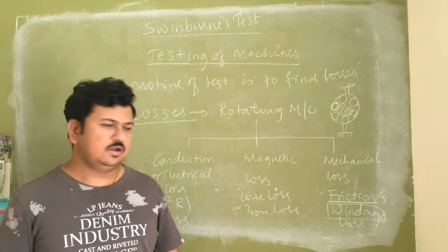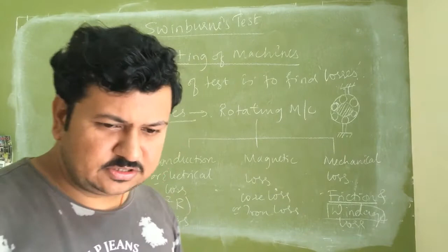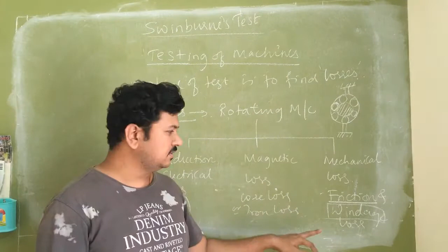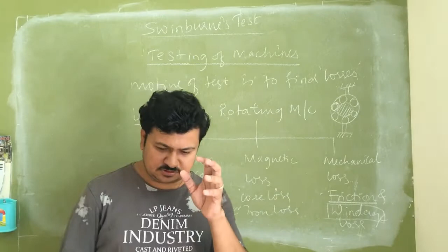Because there is no contact between the stator and the rotor in the air gap. Then why is there windage loss in the air gap? Windage loss in the air gap is due to the friction between the rotor and the air in the air gap. Please remember this. Don't think that air will not give any opposition to a moving body. Air has substantial potential to oppose a moving body.